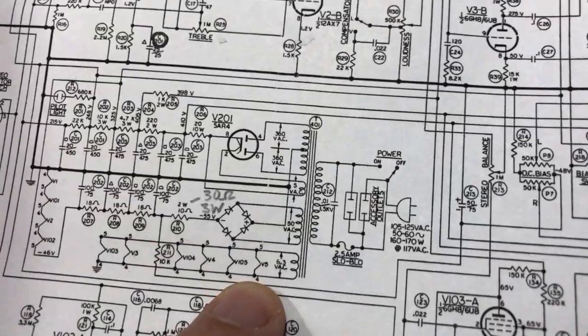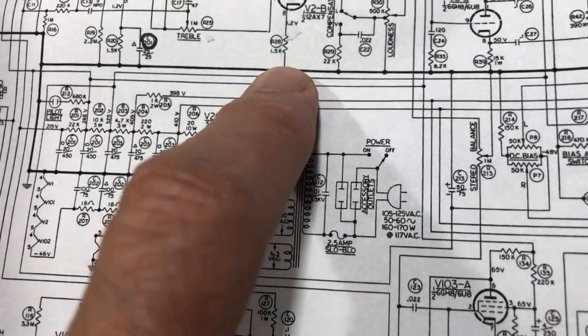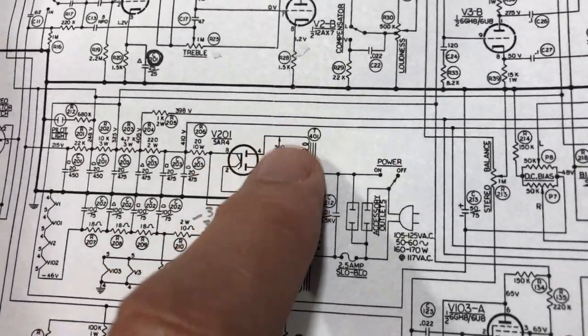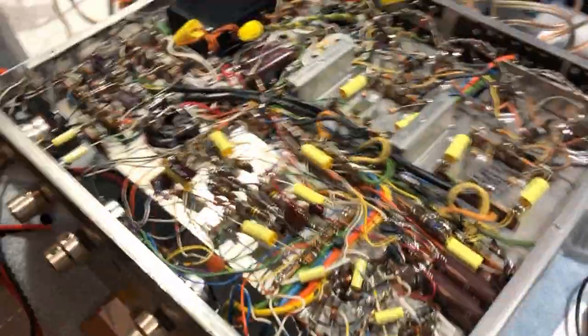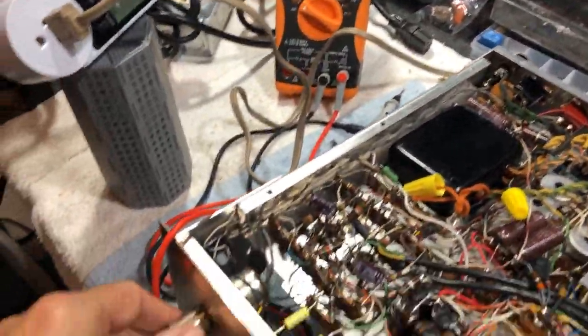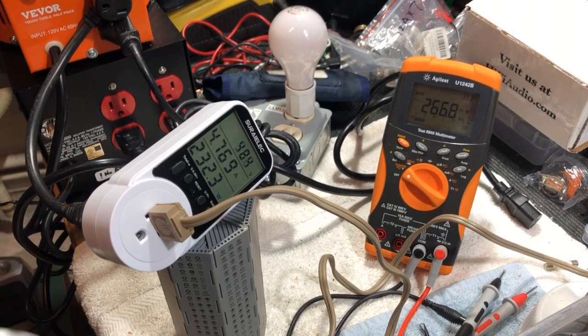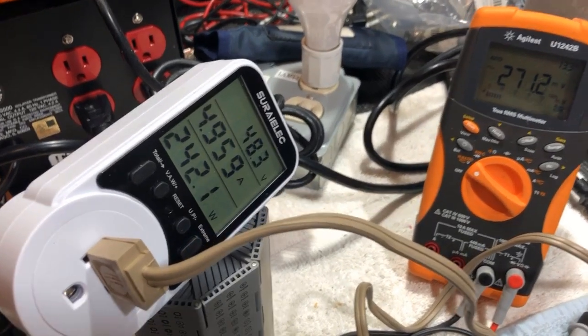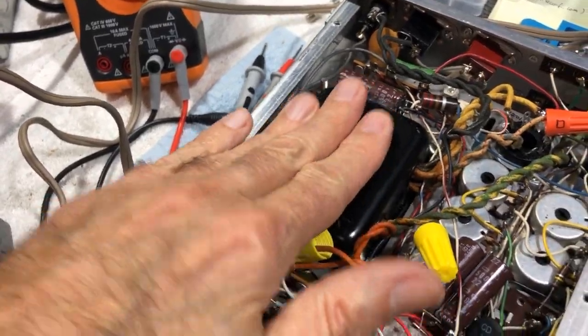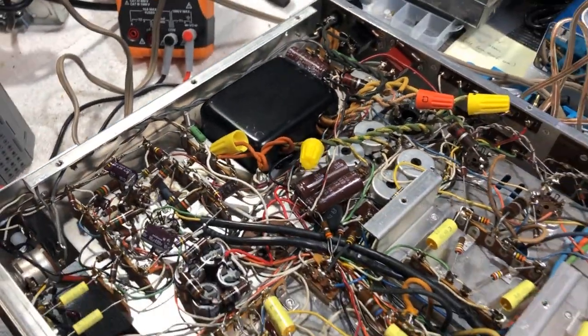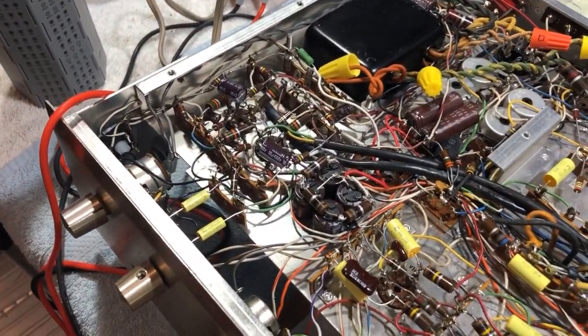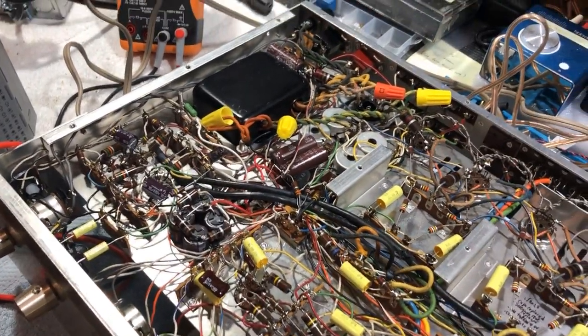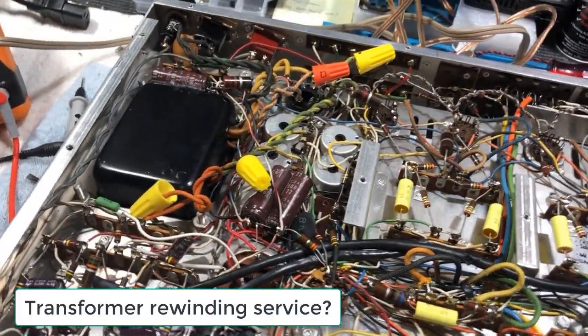I have now isolated all of these transformer outputs, so there is nothing in the circuitry that's connected to the transformer. And when we turn the power on, we still get an enormous power draw. 5 amps, yeah, 240 watts with nothing connected. So yeah, and the transformer will get hot. I'm guessing there's probably a shorted winding in there. That's unfortunate. I'm not sure if that's a part I would be able to find.